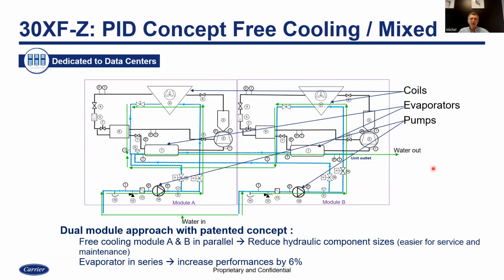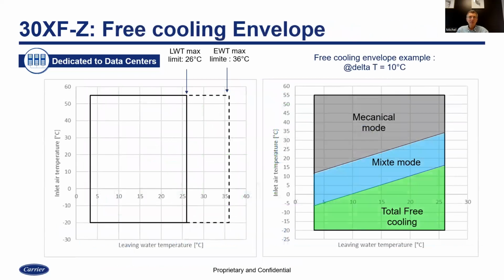So it means that by playing with those two valves, we can send water to hydronic coils or directly to the evaporator, and water afterwards always goes through the heat exchanger. If additional cooling is needed, it will be provided by compressor one or two. In some modes, if only a very small amount of additional cooling is needed, this compressor may be closed, and the only capacity from the mechanical part will be provided by this. Okay, now we have the notion of free cooling operating envelope.